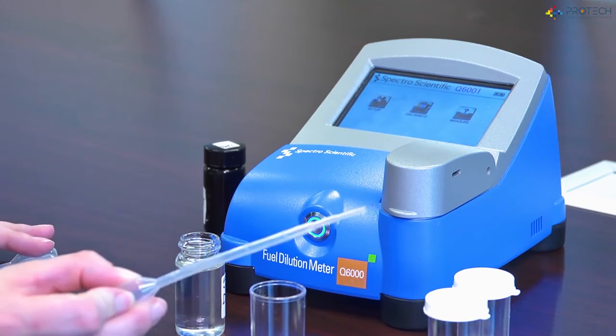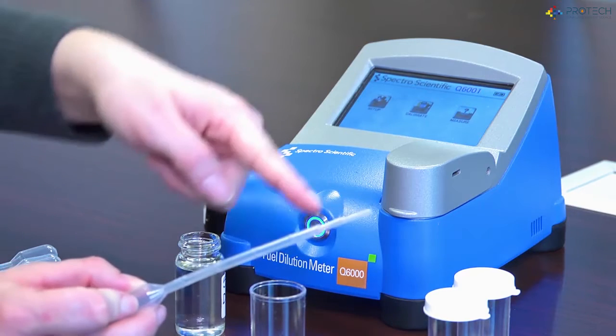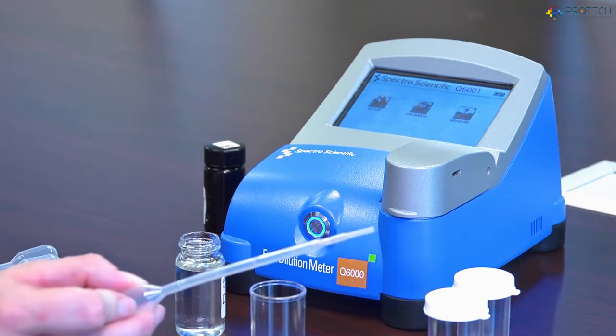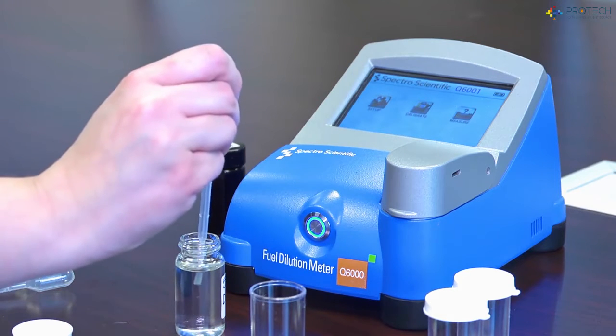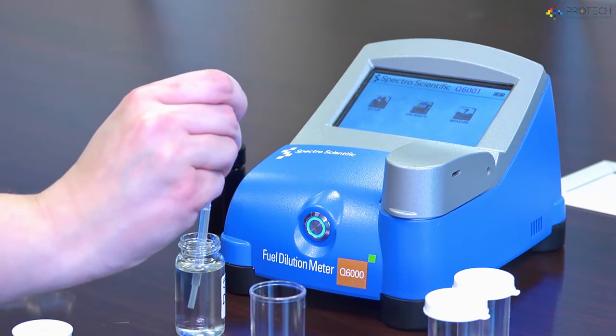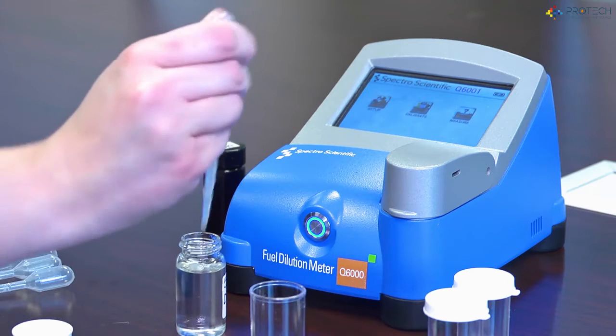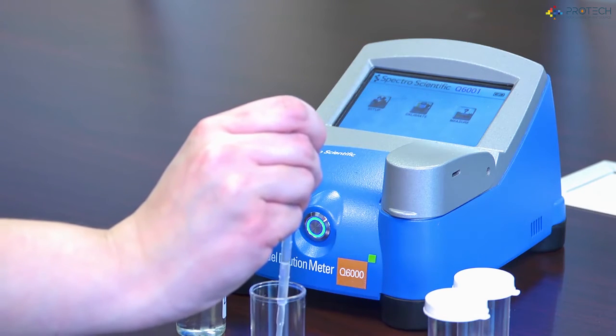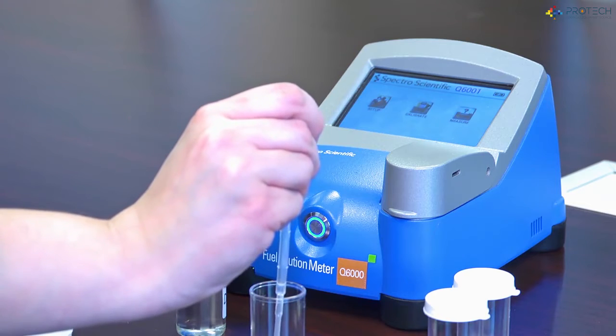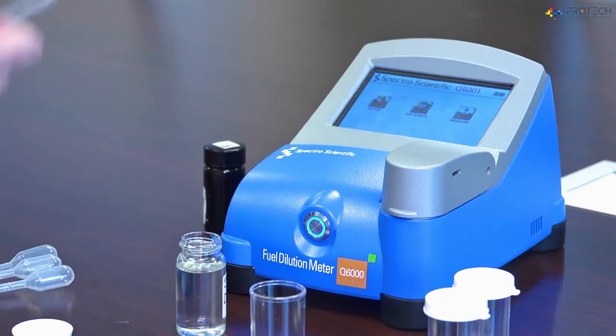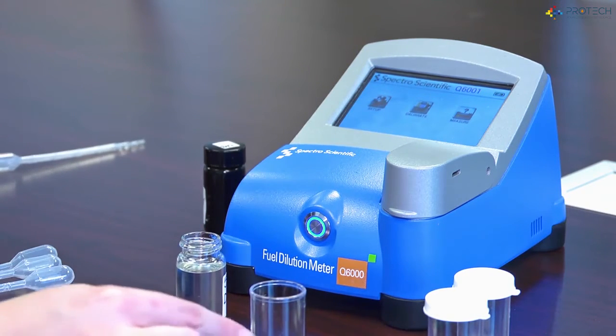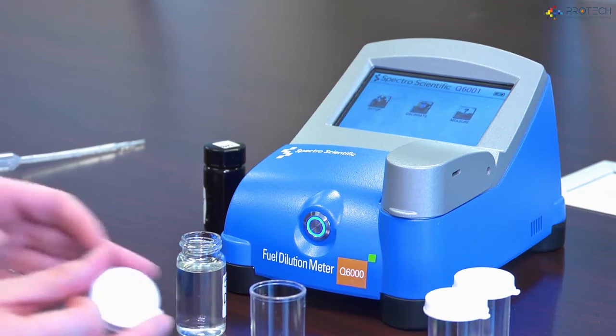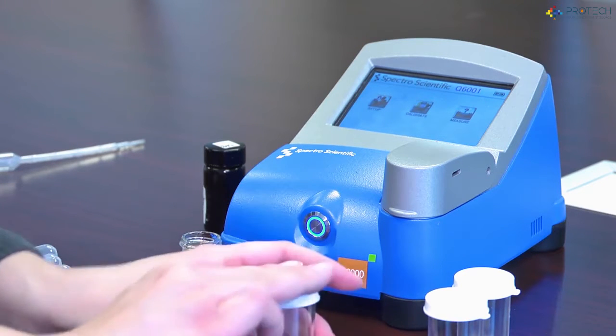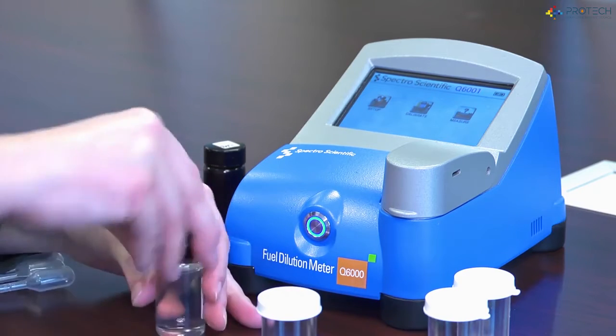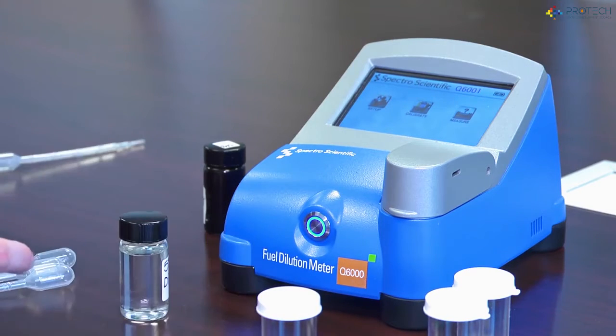We use graduated disposable transfer pipettes, and each mark is 0.25 mils. I need about a half mil to put in my sample vial. The amount of volume is not critically important, so I'm going to fill it about to the line, and then I'm going to slowly dispense it onto the felt pad. I'm going to be careful not to get any liquid on the side of the vial or touch my pipette tip to the pad. So I'm going to cap my vial, and I need to let it sit to equilibrate for about a minute.